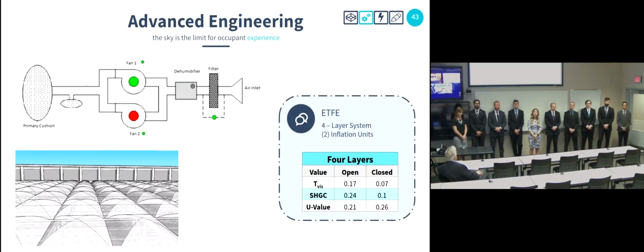We were able to come up with a compromise of a 4-layer ETFE system. This system has 2 inner layers that can open and close based on the time of day. As you can see, we were able to input the solar heat gain coefficient values into our energy model to ensure it didn't impede our savings. The ETFE is inflated by 2 inflation units, each unit containing 2 fans, but only one of which is running at a time. The only reason for these inflation units is to maintain pressure in the cushions, not keep airflow going through it continuously.